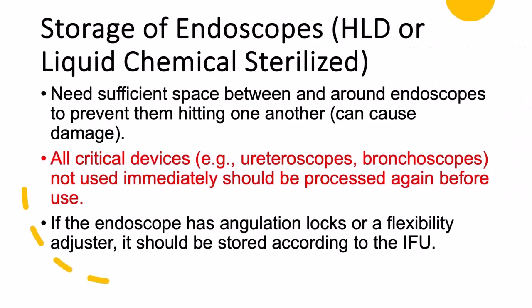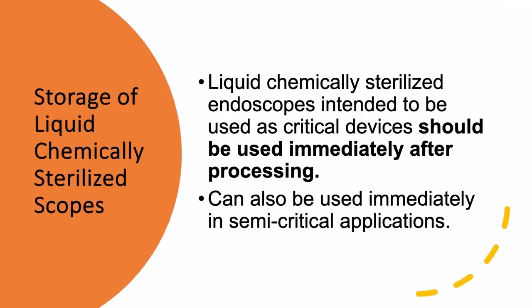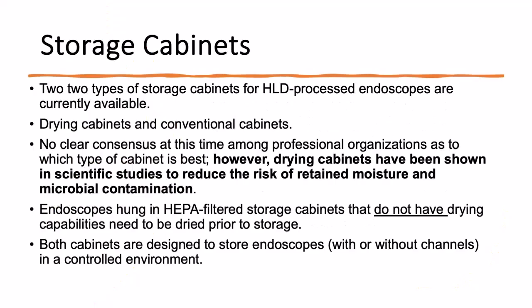You need sufficient space between and around your endoscopes to prevent them hitting one another, which can cause damage. All of your critical devices, such as your ureteroscopes and bronchoscopes, not used immediately, should be processed again before they are used. And if the endoscope has an angulation lock or a flexibility adjuster, it should be stored according to the IFU. Liquid chemically sterilized endoscopes intended to be used as critical devices should be used immediately after processing. And they can also be used immediately in semi-critical applications, so you don't want them sitting around in the processor. Storage. There's two types of storage cabinets for high-level disinfected processed endoscopes: drying cabinets and conventional cabinets.